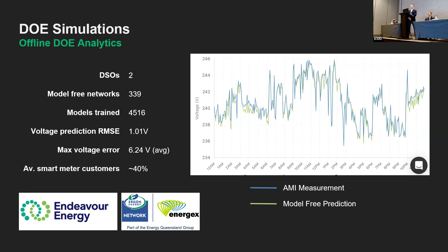amount. The slide just provides some details on what was put into the actual optimization. The key things there: the objective is to maximize exports, so only curtail when you need to curtail. The constraints: there's an upper steady state limit in Australia of 253 volts, which can be set to whatever is appropriate. The thermal constraint is that the aggregate exported energy should not exceed the kVA rating of the distribution transformer. And for the customer, the minimum amount that we curtail to is 3 kilowatts, and the maximum allowed is 10.